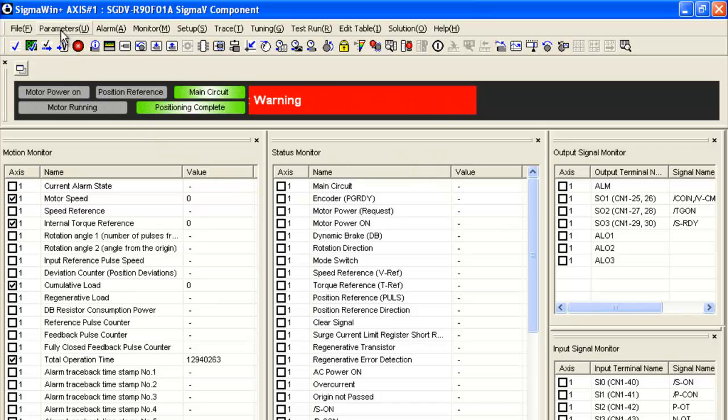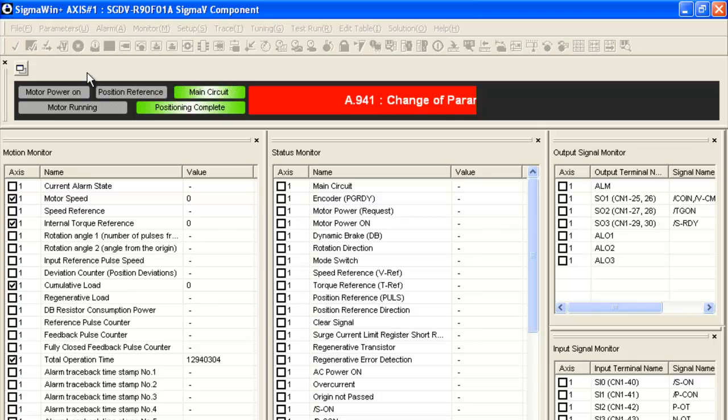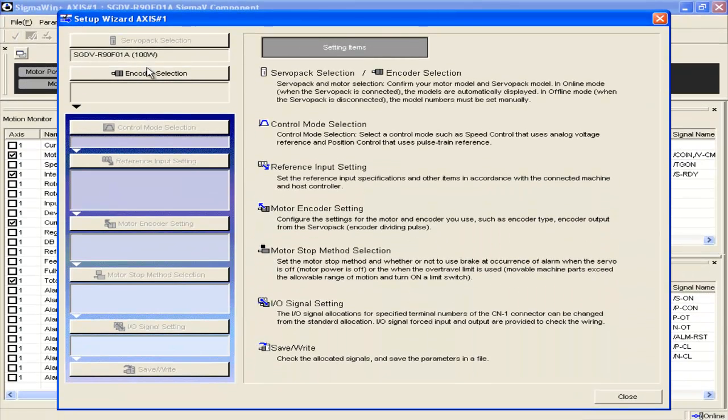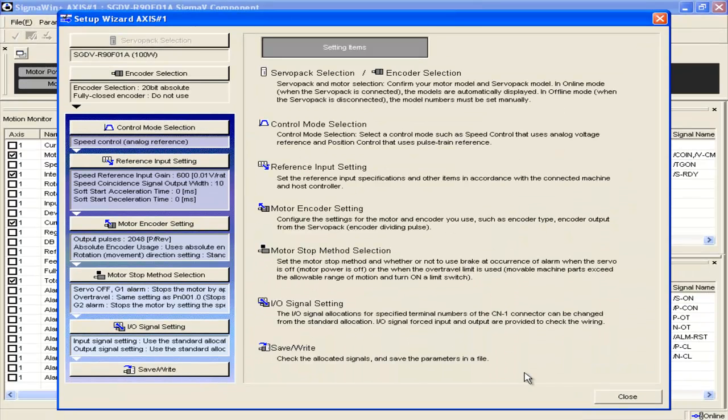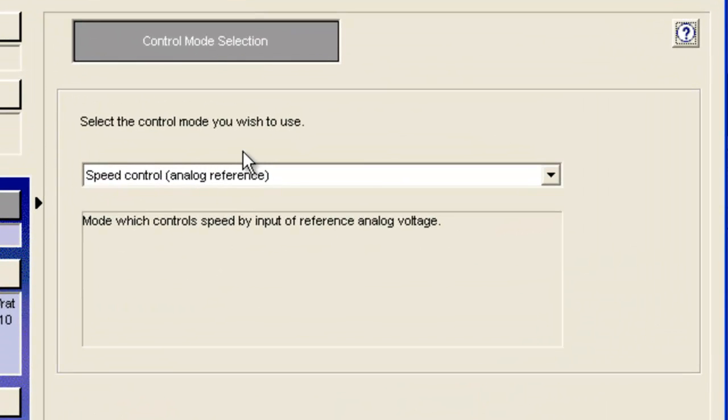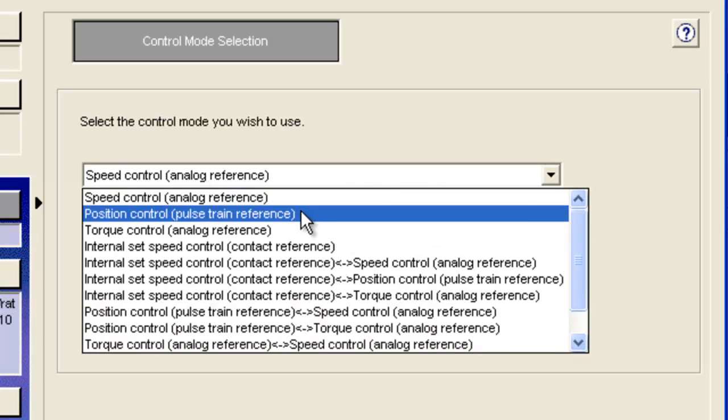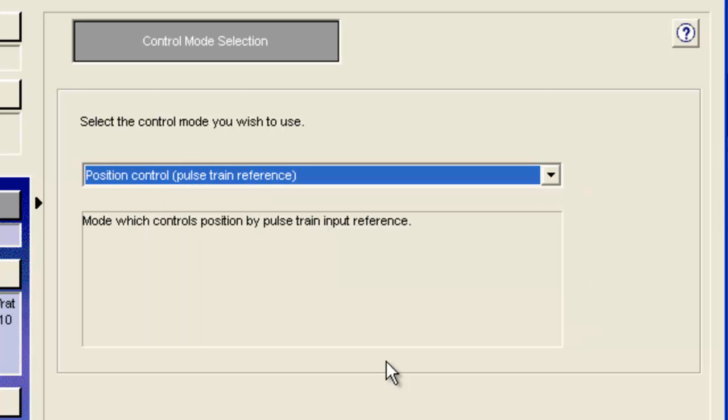So now let's start the wizard by going to setup wizard under the parameter menu. And the first step is always to do this apply to not using the fully closed encoder. Under control mode, I select position control, the pulse train reference, and hit apply.